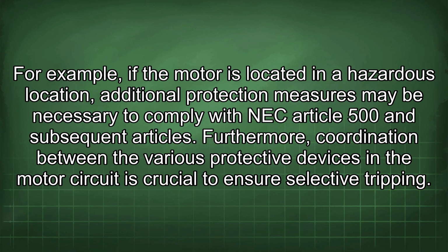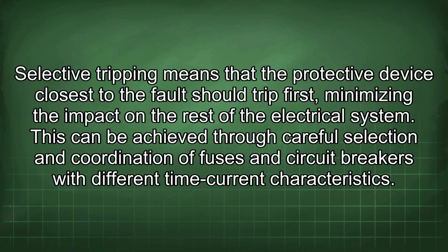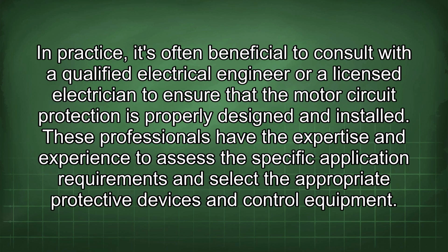Furthermore, coordination between the various protective devices in the motor circuit is crucial to ensure selective tripping. Selective tripping means that the protective device closest to the fault should trip first, minimizing the impact on the rest of the electrical system. This can be achieved through careful selection and coordination of fuses and circuit breakers with different time current characteristics. In practice, it's often beneficial to consult with a qualified electrical engineer or a licensed electrician to ensure that the motor circuit protection is properly designed and installed.